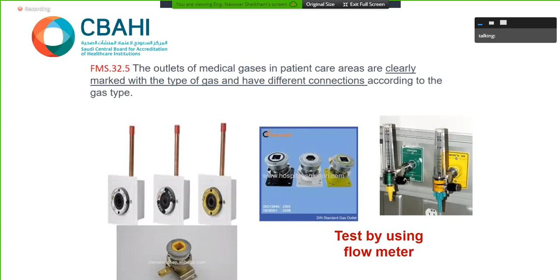Actually, I have intentionally put this slide because it's a disaster for us and for the hospital to see hospitals using outlets that are forbidden to use. For instance, in the left photo, it says medical air, don't use outlet, system under test, and they are using it and did not remove this sticker. Not removing this sticker means maintenance or testing was not done. The other photo says this point must not be used because it is under testing, danger, and they are using it. So please remove this sticker after maintenance, testing, or replacement.